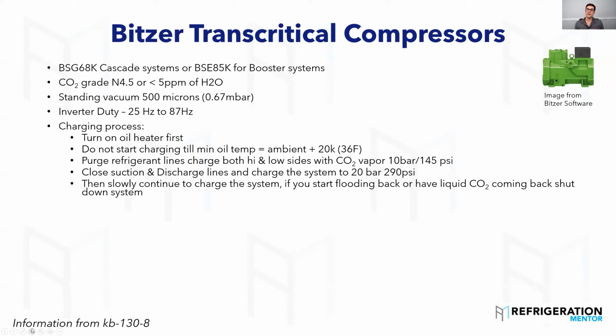So what you need to do is charge the system with vapor. When you evacuate it, you get it down and you start to charge, you need to charge with vapor first, because we talked about it earlier, dry ice. Dry ice is anything below the triple point, which is 75 PSIA. You want to make sure you have enough vapor. Bitzer says 145 PSI or 10 bar. Copeland says a similar thing. Some OEMs will say 100 PSI or 120 PSI, which is just under 8 bar, 9 bar, 10 bar. But the big thing is, I've started CO2 units at 100 PSI of vapor. You just need to make sure that whole system has vapor in it, because you don't want one section all of a sudden getting plugged with dry ice.